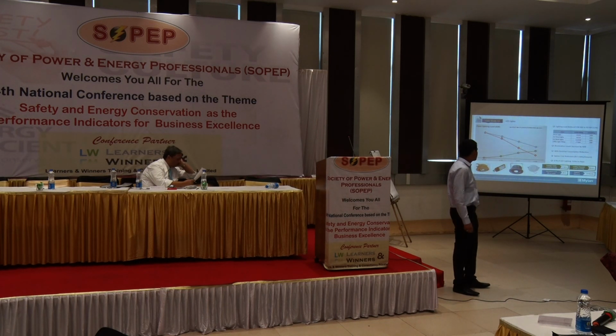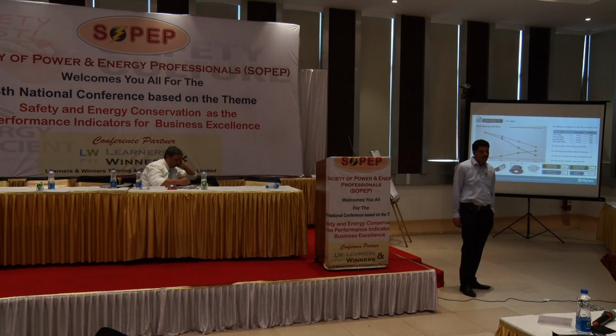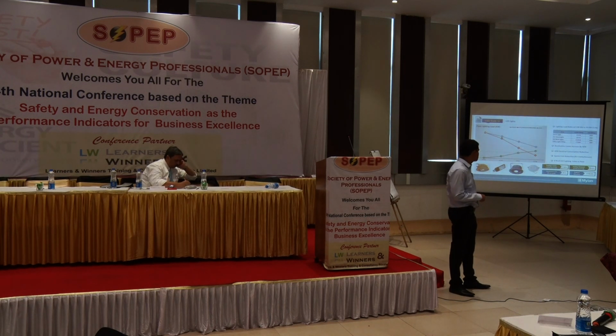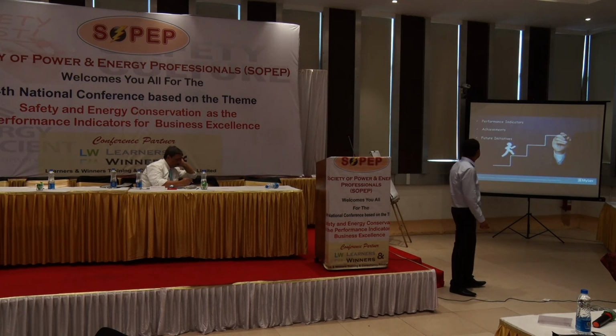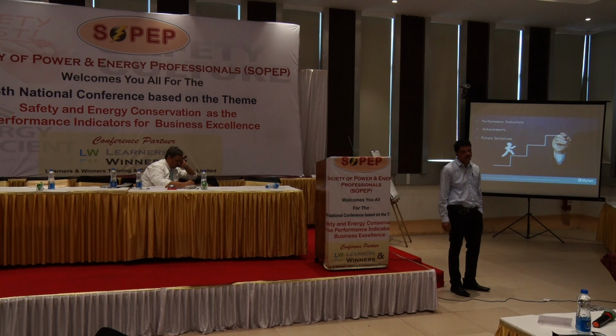So we have targeted to replace all lightings with LED lighting. 51% we have achieved as of now. Earlier our lighting load was 198 kilowatt. Now it has come down to 99 kilowatt. With this, payback is 20 months. Investment is 3.86 lakhs. So these are the performance indicators, achievements, and future initiatives we are talking about.